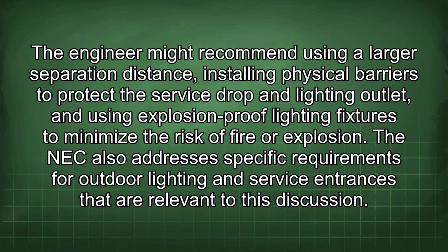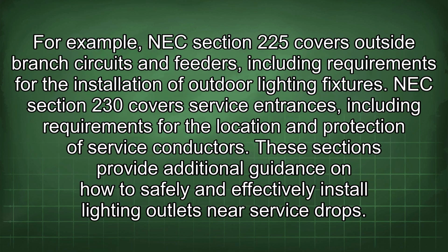The NEC also addresses specific requirements for outdoor lighting and service entrances that are relevant to this discussion. For example, NEC Section 225 covers outside branch circuits and feeders, including requirements for the installation of outdoor lighting fixtures. NEC Section 230 covers service entrances, including requirements for the location and protection of service conductors. These sections provide additional guidance on how to safely and effectively install lighting outlets near service drops.